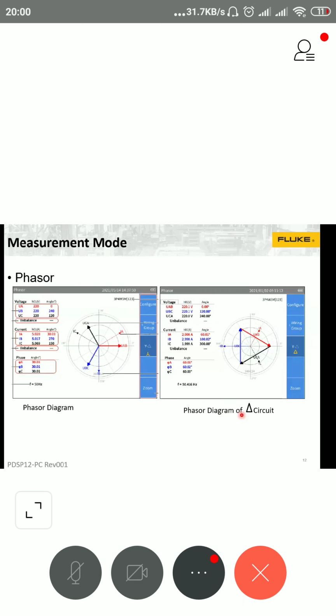So these are some of the sample screenshots of how the instrument looks. Now you can look at the vector diagram. The vector diagram also shows the phase angle differences between voltage and current, and this indication is for the star, and this is for the delta connected circuit. Not only that, you can also look at the unbalanced values.